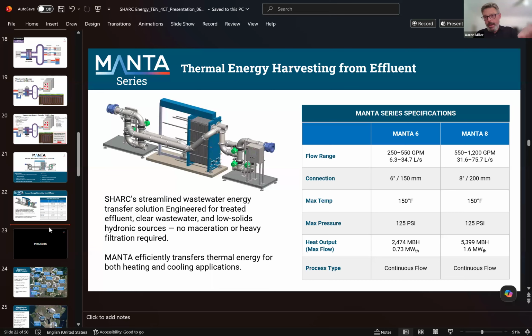If you're doing SHARC or Manta, you're dealing with a much larger flow rate. So think about a sewer that runs by your building or a wastewater treatment plant. You're getting 3 to 5 million gallons a day, right? Of that, I'm only working with a very small portion of the flow. And then my heat exchanger is designed for a 10-degree delta T, meaning I'm either taking 10 degrees out or putting 10 degrees in at any given moment. I can go up to 15 or 18, but usually it's about 10 or 12 degrees. So it's a fraction of a fraction.